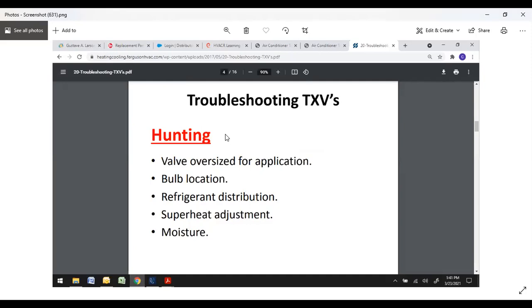TXVs that hunt, this is not uncommon. You can usually see that because your suction pressure will jump up and down a little bit. If you see it hunting, just let it go. It should find its happy place shortly, hopefully. If it keeps on hunting, the valve could be oversized for the application. You may have the bulb in the incorrect location, which we'll get into in just a few minutes. Location, insulation, and making sure it's secure are important. Refrigerant distribution, superheat adjustment. Like I said, most of the residential are already preset, or you could have a lot of moisture and contaminants in the system.